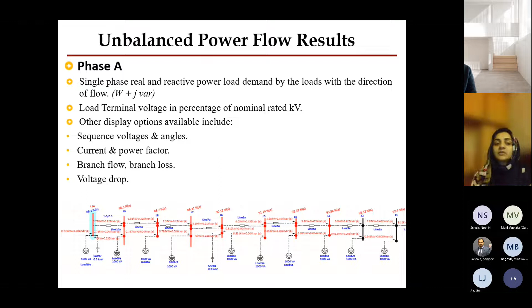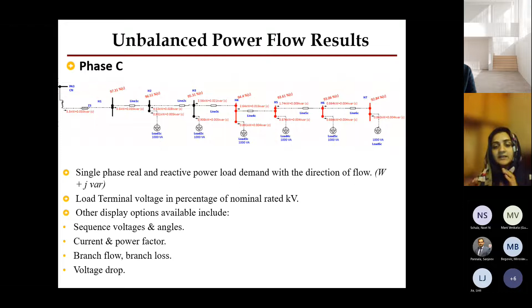These are the results for phase A, and for phases B and C, which are for the unbalanced power flow. These are the results for three-phase load, for the four three-phase loads connected, and we can see how much power is flowing among the nodes, the voltage magnitude, and voltage angle as well. We can see the voltage drop among two lines. There are multiple options in ETAP that let us determine whatever we want to see, such as voltage angles, voltage magnitudes, power flows to the loads, and if we have capacitance, how much reactive power is being supplied, and things like that.